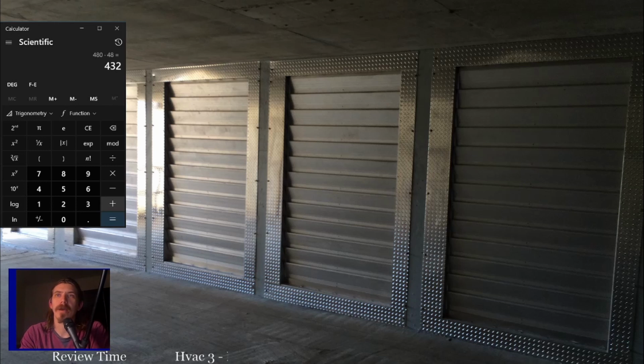But you can't have 430 on one terminal, 470 on another terminal, and 510 on another one. Nah. It's plus or minus 10%, but you don't have the correct balance. You don't have balanced phases. So phase imbalance is not plus or minus 10. That's plus or minus 2, but the voltage itself is plus or minus 10. All right.